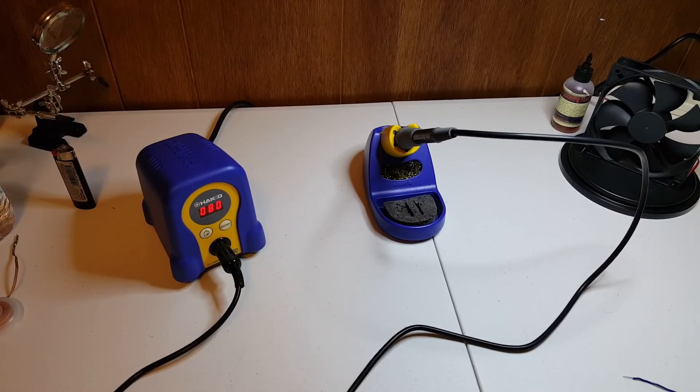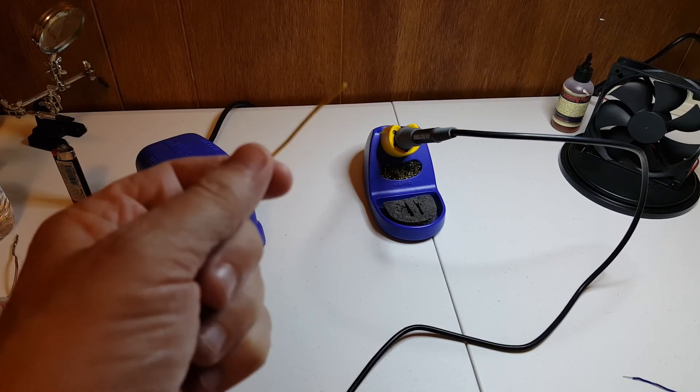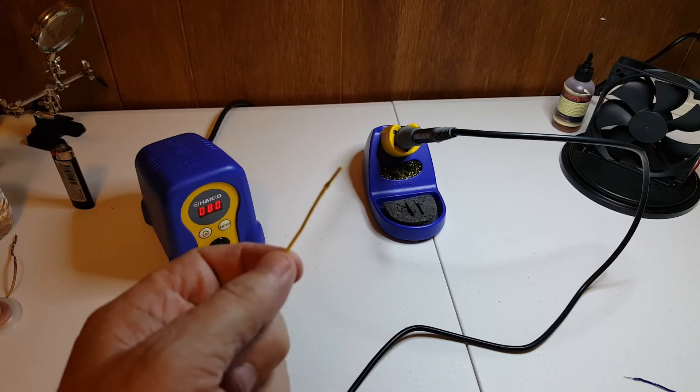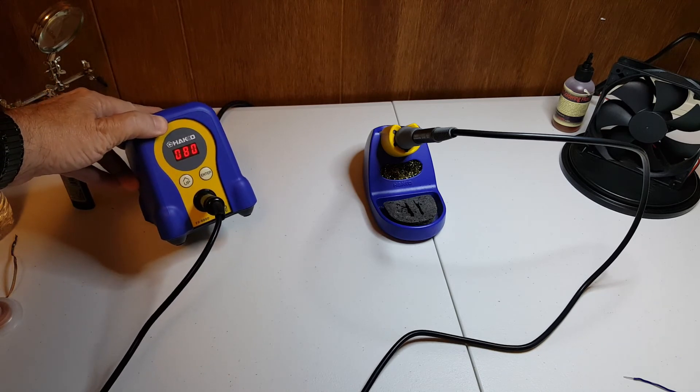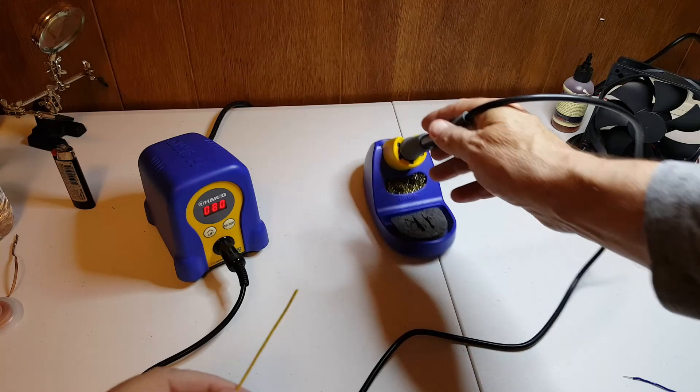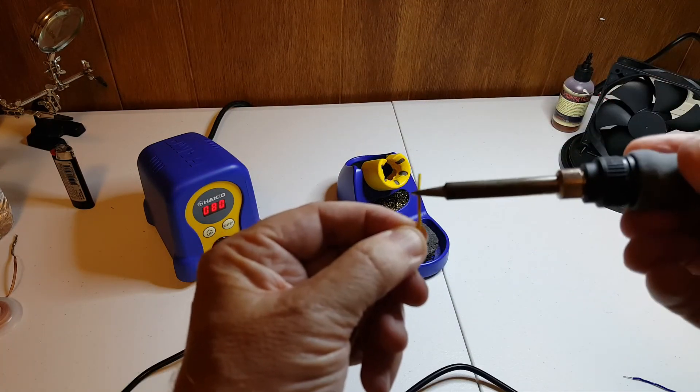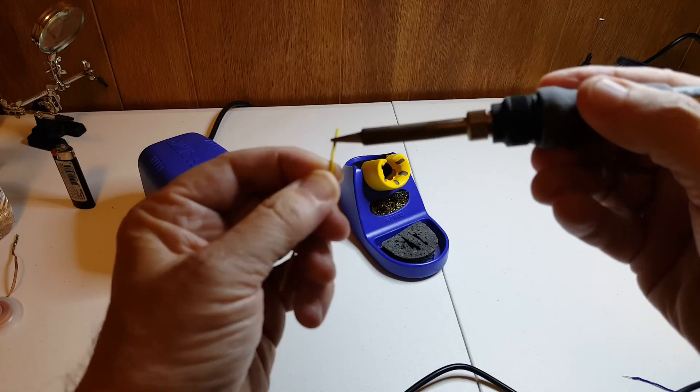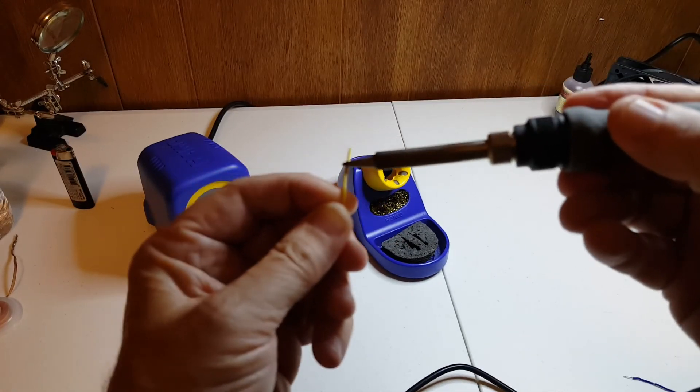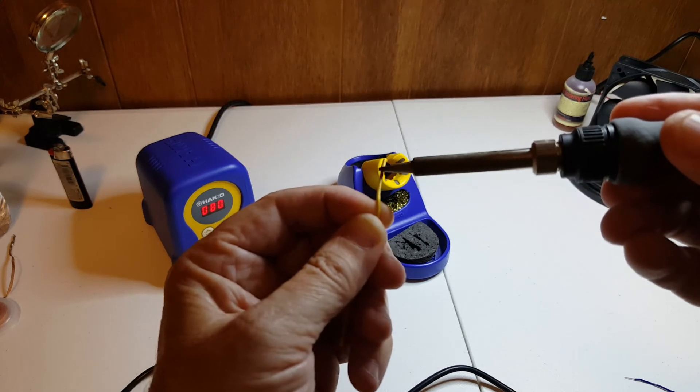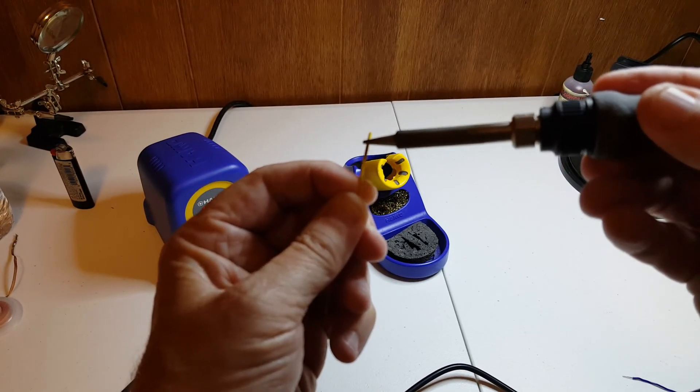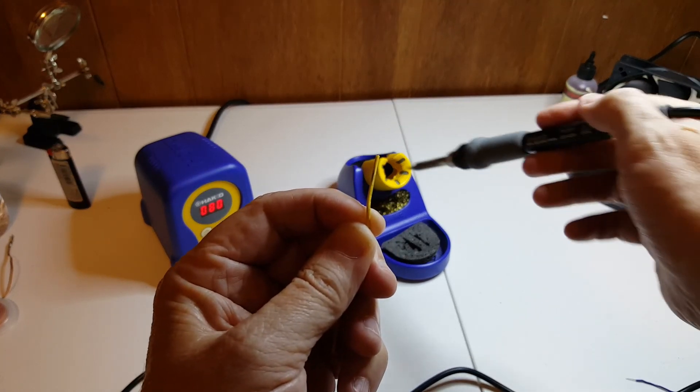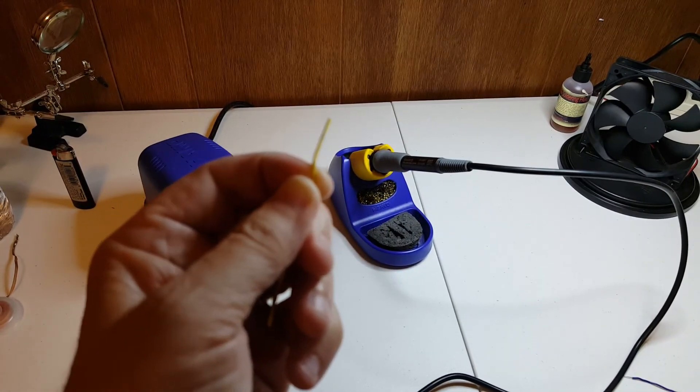Okay, so since this PVC insulation is rated at 80 degrees C, I thought what I'd do is I'd take my soldering iron. And you see, I've got it set to 80 degrees C. And I'm going to apply the soldering iron to the insulation to see what happens. So, I'm applying the 80 degrees C directly to the insulation. And I'm not sure if you'll be able to see this, but really there's nothing happening. It's just sliding along. It's not melting. So, 80 degrees C doesn't do much. Well, maybe if we apply a higher temperature.